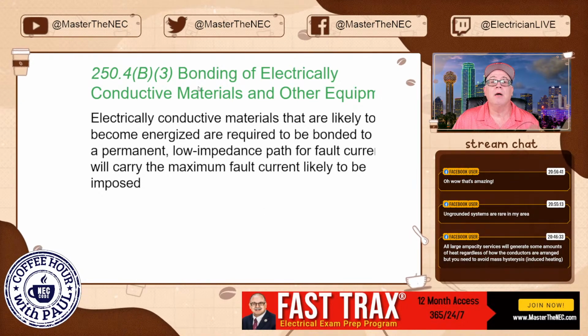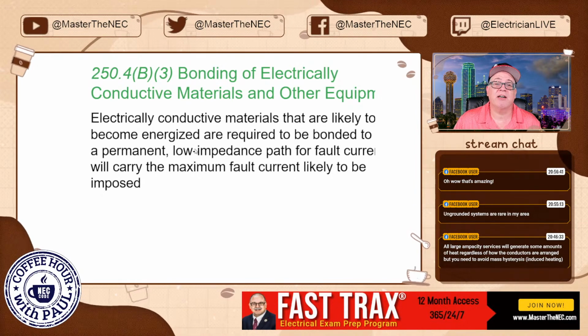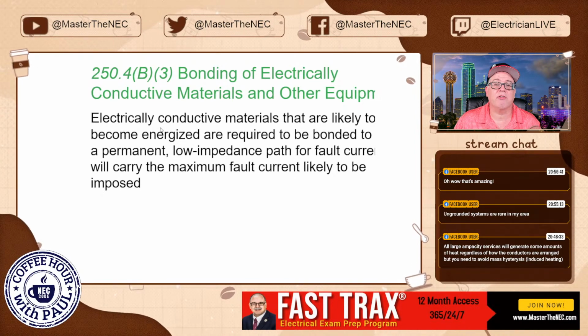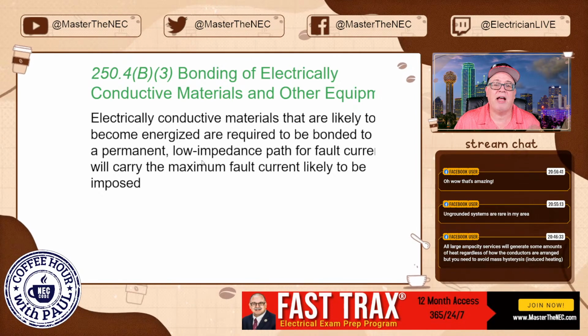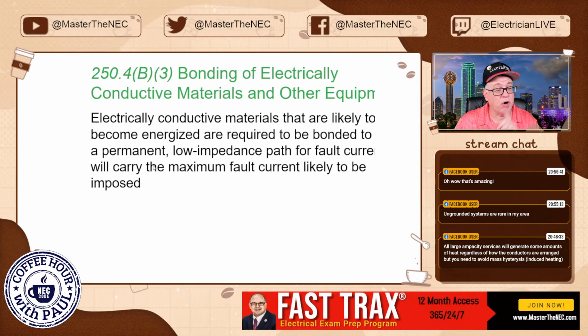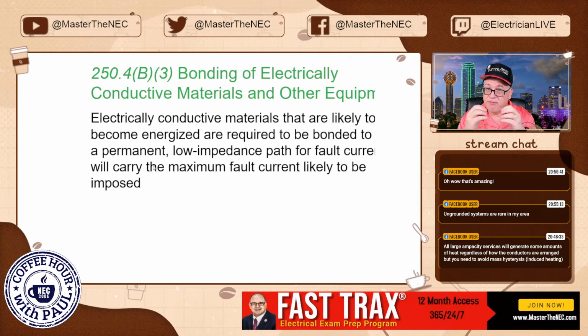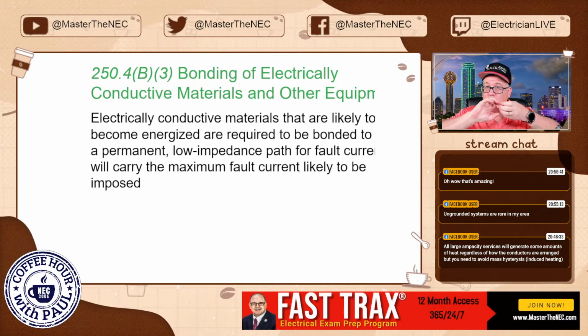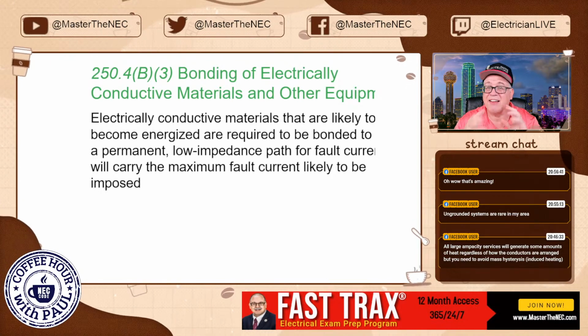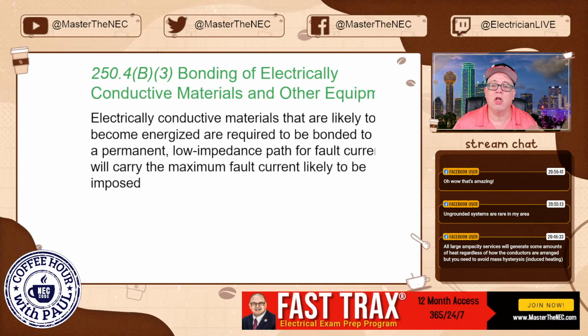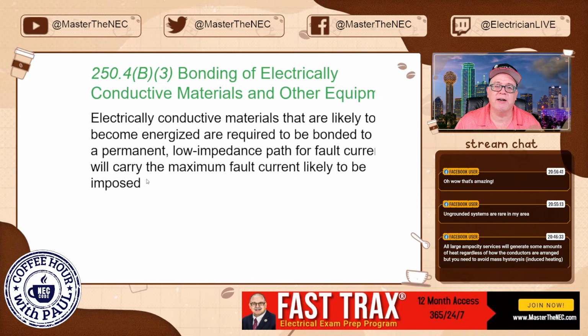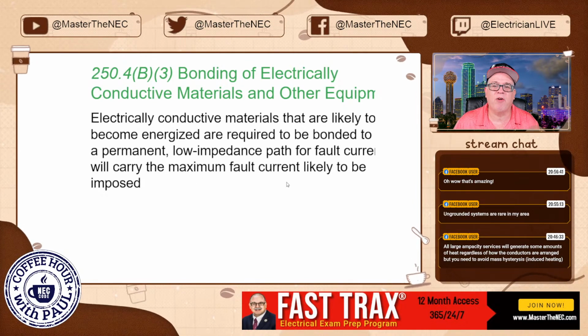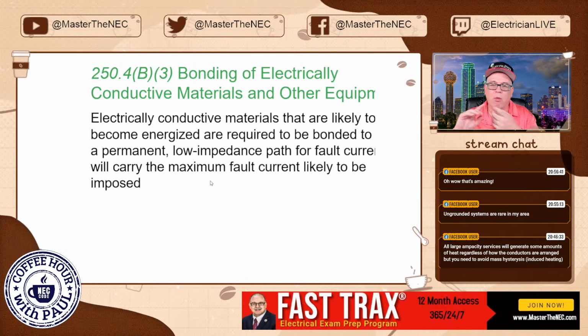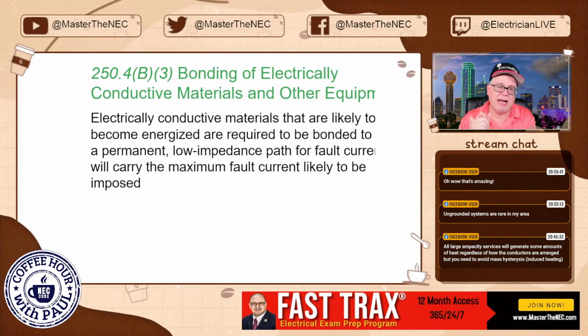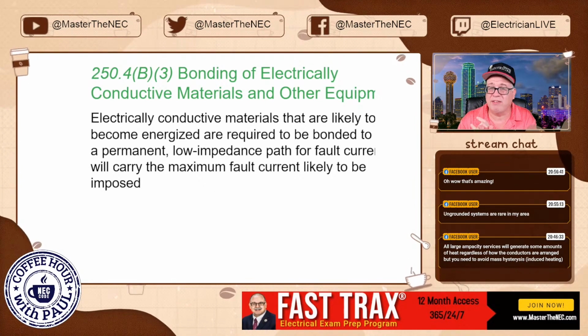All right. Bonding of electrically conductive materials and other equipment. Electrically conductive materials that are likely to become energized are required to be bonded to create a permanent, again, fittings, make everything upright, wrench tight, do what you have. It's got to stay there. It's a permanent, low impedance path for fault current that will carry the maximum fault current likely to be imposed. When we say maximum fault current, that means you've got to know how to do the sizing. You've got to know what's involved.